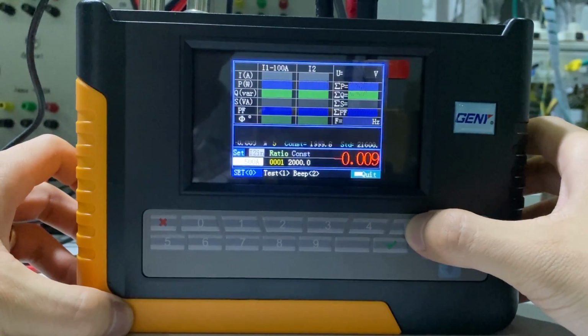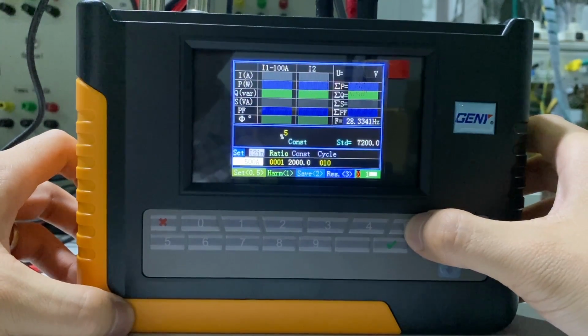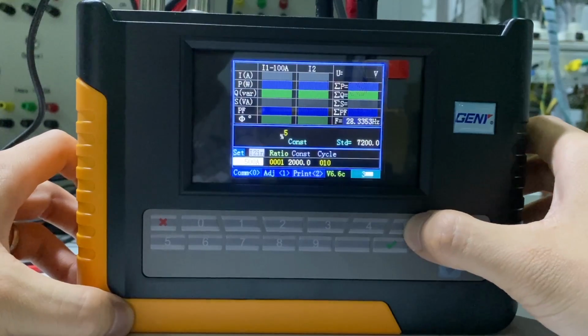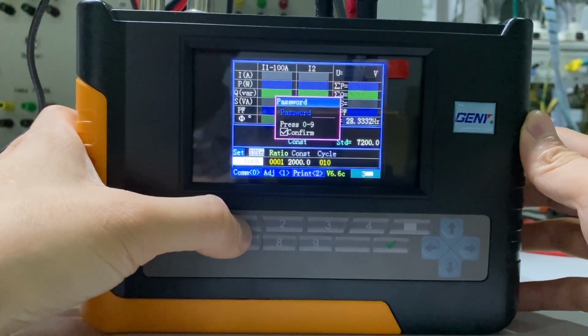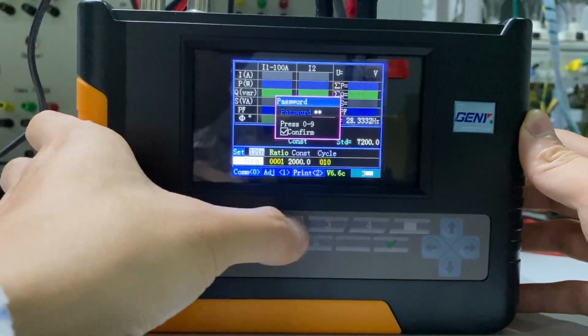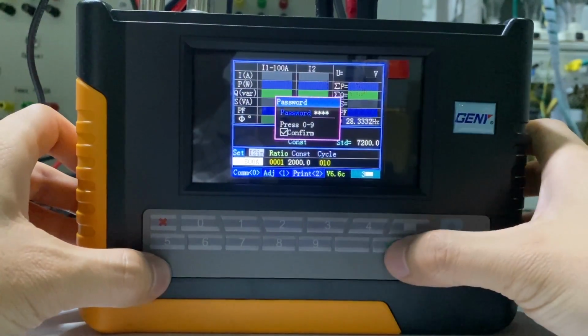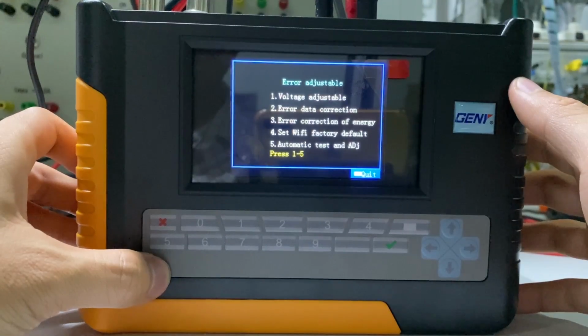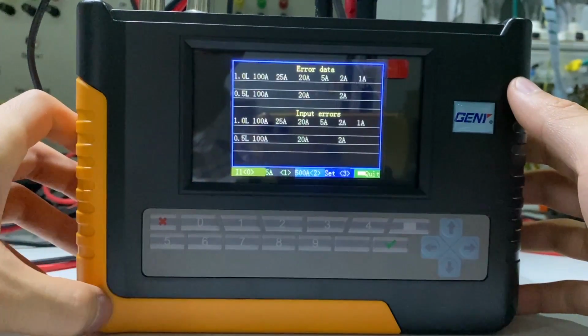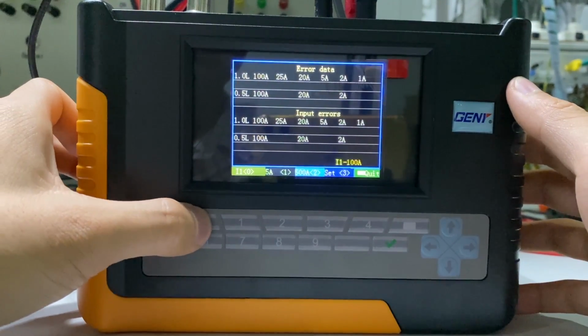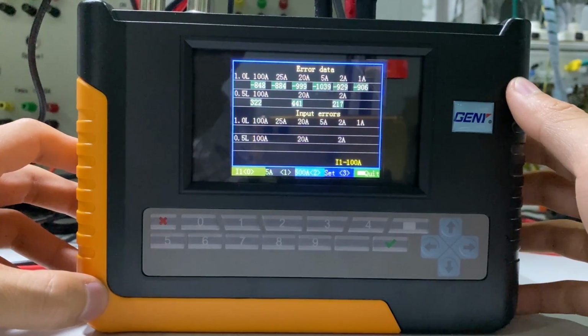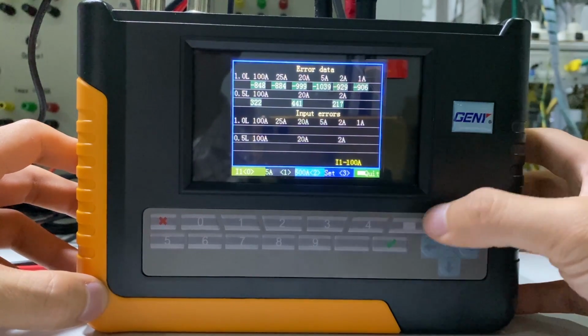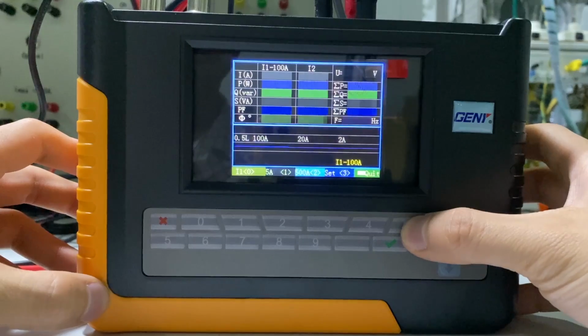Enter the calibration menu again. Select calibration. Enter the password again, 1234, and confirm. Enter the second interface and select the second option to view the calibration parameters. If the parameters have changed compared to before the calibration, the calibration is successful. Press the white button to exit the page.